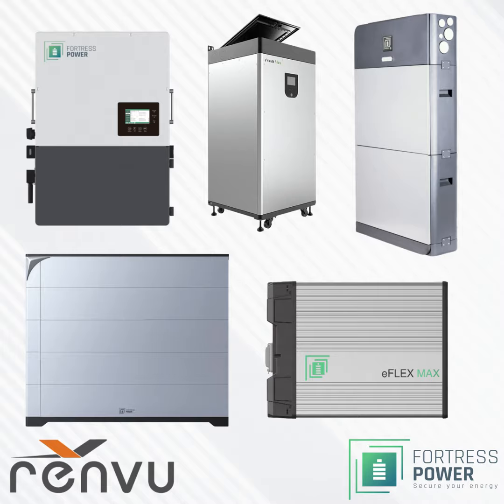The name, I wouldn't say it's misleading, but folks think that it's just a small 12 kilowatt inverter. I'm like, absolutely not. This thing's a huge inverter, but when the grid goes off, we can deliver true 12 kilowatts of power, right? So it's stackable in 10 units. It's outdoor rated, 120/208 volt compatible or 120/240 with the transformer built in on or off grid. So please note that when you say Envy True 12, that means when it's off grid. When it's on grid, it can deliver up to 18 kW, right?